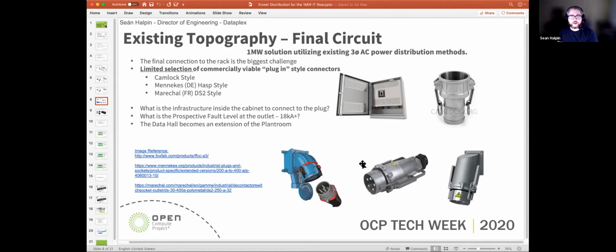And then there's the Marechal version. Your standard IEC connector usually goes up to about 125 amps, and anything above that you're moving into more marine and aeronautical connectors, certainly at AC. But the main thing we need to concentrate on here is the fault current as well.